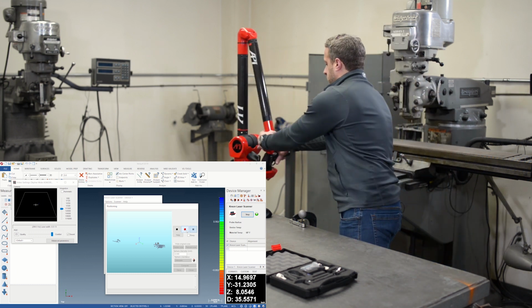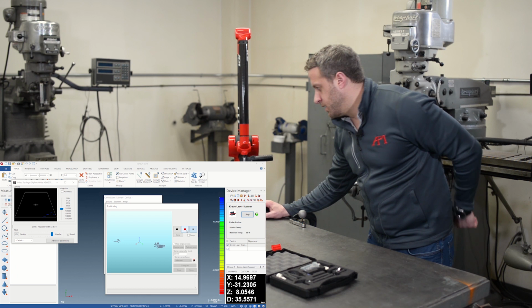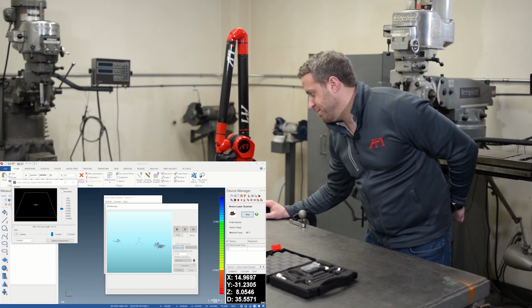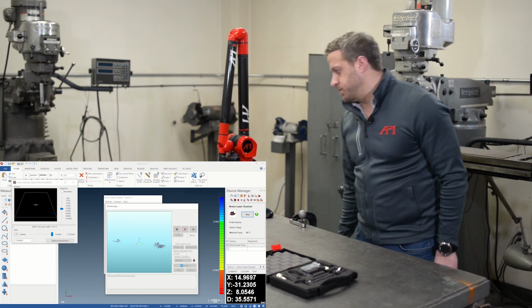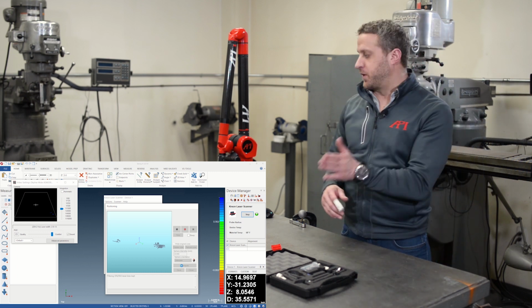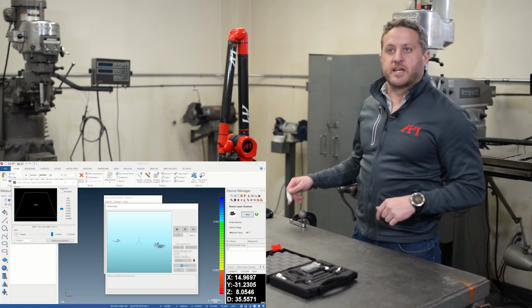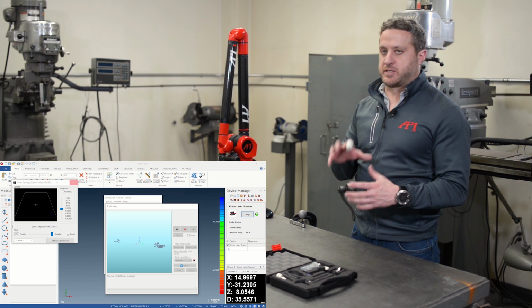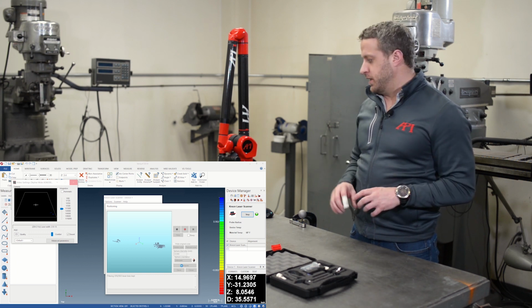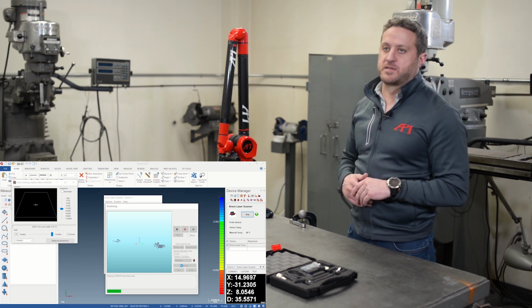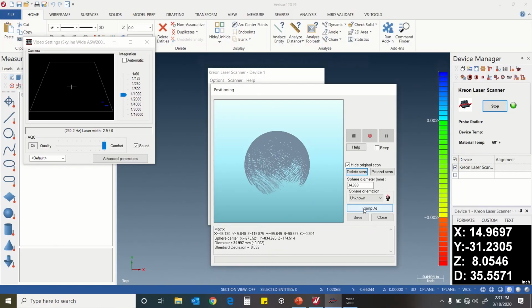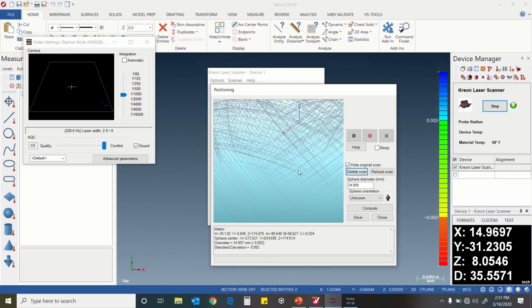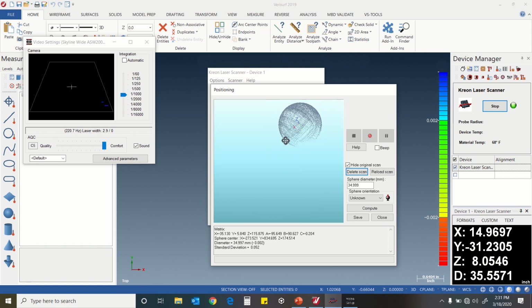When we're done, we'll stow the arm, we'll press stop, and we'll hit compute. So right now it's filtering out a lot of the flyer data, table, clamp, and it's trying to pull out that sphere, and it's going to calculate it and give us our results of the calibration. So after it computes the sphere, you can see that it pulled out quite a bit of the sphere. We can zoom in, we can see what kind of data it collected.